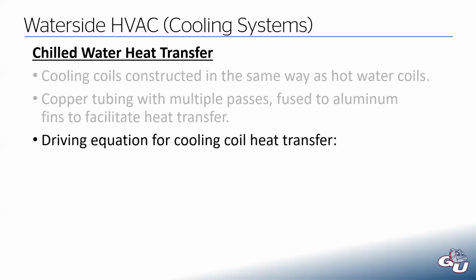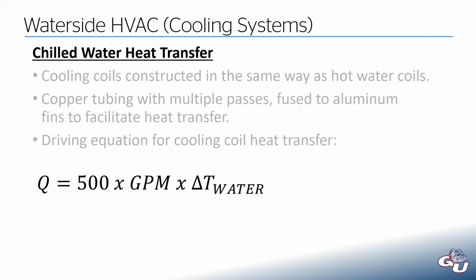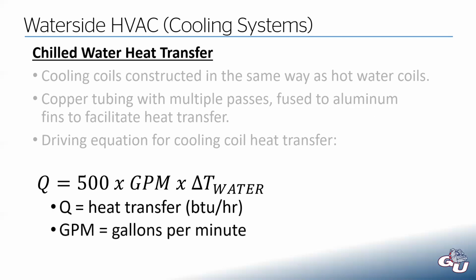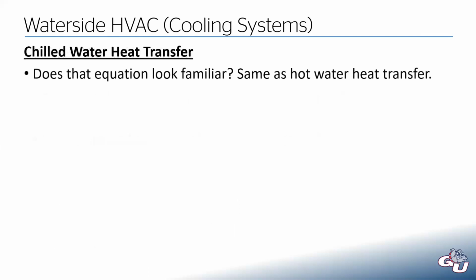Our driving equation is Q equals 500 times GPM times the delta T of our water. Q being our heat transfer in BTU per hour. GPM is our water flow in gallons per minute. And then the delta T is the temperature of our water going in versus coming out. And that should look very familiar because that's the same equation we used on the heating side. So same exact equation.